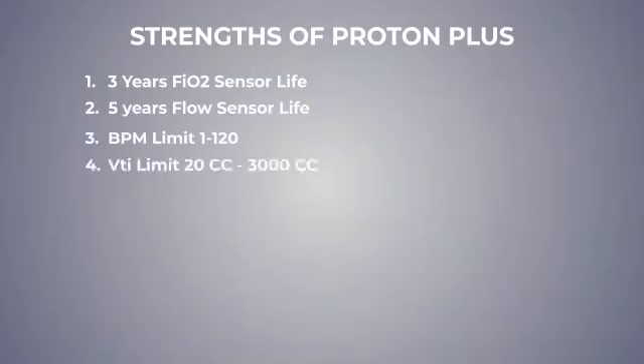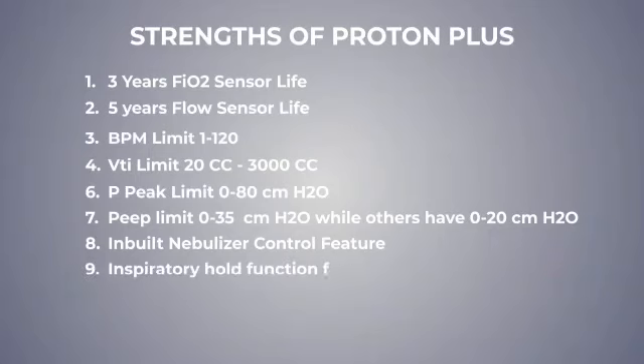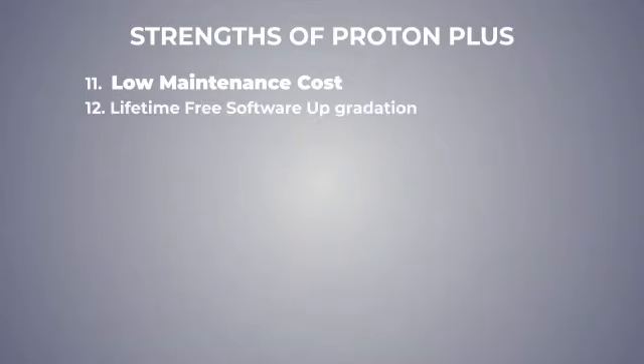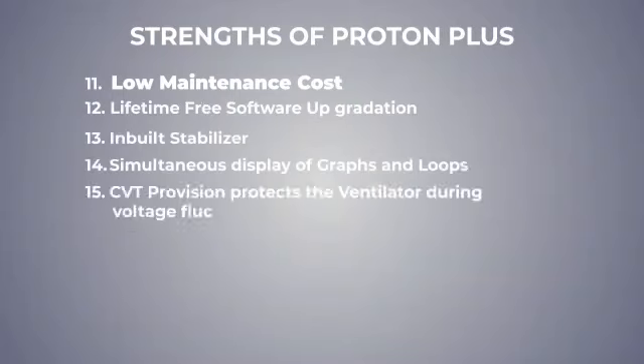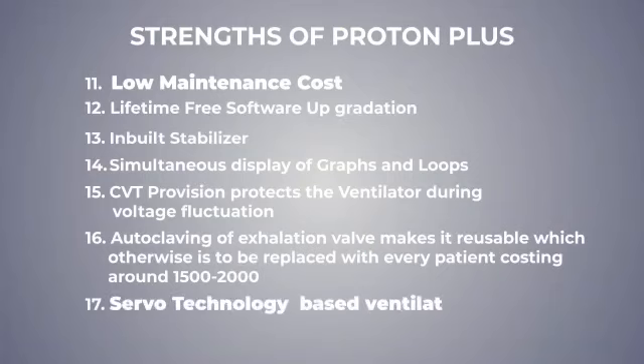Key strengths include: VTI limit 20cc to 3000cc, P Peak limit 0 to 80 centimeter H2O, PEEP limit 0 to 35 centimeter H2O while others have 0 to 20 centimeter H2O, inbuilt nebulizer control feature, inspiratory hold function for measuring plateau pressure and static compliance, easy operation and selection of parameters, low maintenance cost, lifetime free software upgradation, inbuilt stabilizer, simultaneous display of graphs and loops, CVT provision protects the ventilator during voltage fluctuation, autoclaving of exhalation valve makes it reusable which otherwise is to be replaced with every patient costing around 1500 to 2000 rupees, and servo technology based ventilator has high response time as compared to other technology.